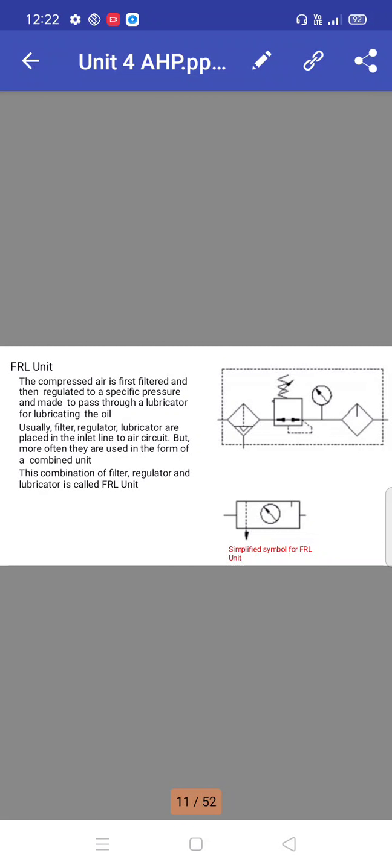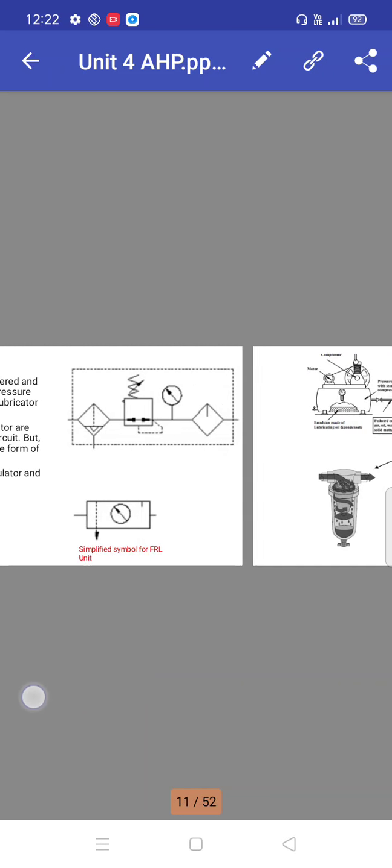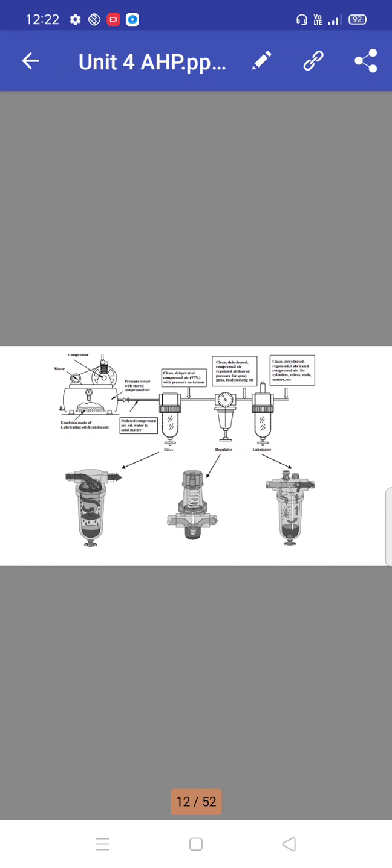That is a FRL unit - filter, regulator, lubricator. It's a combination unit. The compressed air is first filtered and then regulated to a specific pressure, then passes through a lubricator for lubricating. Filter, regulator, lubricator are usually placed inline in an air circuit, but more often they are used in the form of a combined unit. This combination of filter, regulator, and lubricator is called a FRL unit.